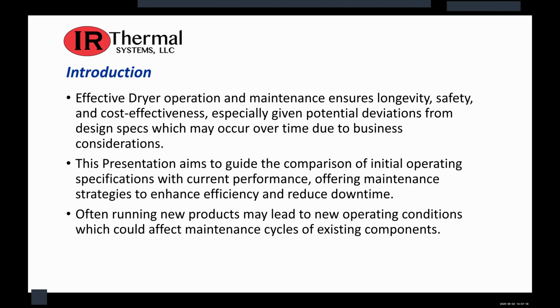As an introduction to this specific presentation, we found that effective dryer operation and maintenance ensures longevity, safety, and cost effectiveness, especially given potential deviations from design specs which may occur over time due to business considerations. This presentation aims to guide the comparison of initial operating specs with current performance. We offer maintenance strategies to enhance efficiency and reduce downtime. Often running new products with existing equipment may lead to new operating conditions, which could affect maintenance cycles of existing components. That's really important to consider because a lot of times what you're making changes over time. A lot of your dryers tend to be there for a long time because they are large capital expenses. But your products might change over time, and especially as new materials and new ideas come in, you might be making adjustments with your existing equipment.